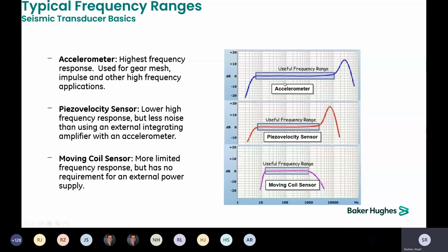So accelerometers generally have the widest usable frequency range. Higher frequencies are kind of its sweet spot. Piezoelectric velocity sensors have a smaller useful frequency range, but are better down at the lower frequencies. Moving coil, again, lower frequency, and also does not have a need for an external power supply.